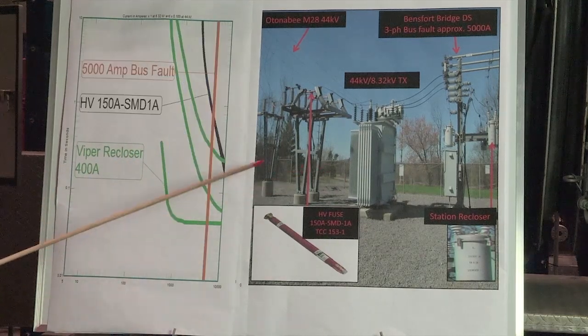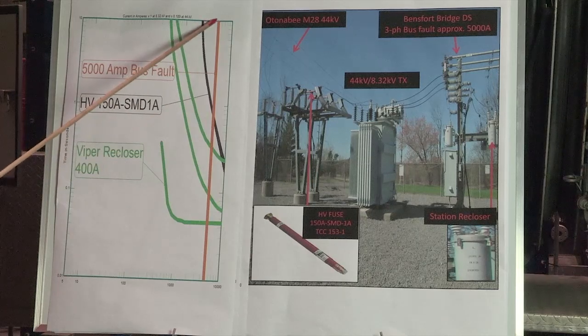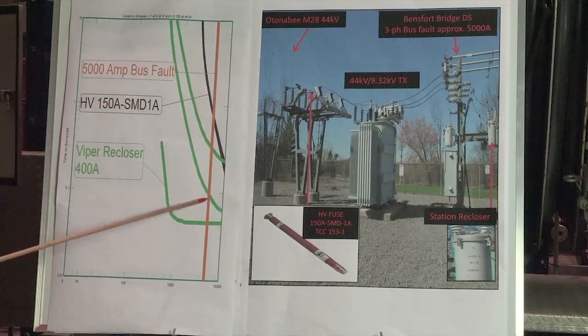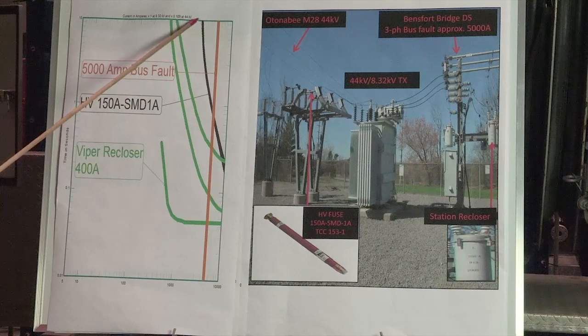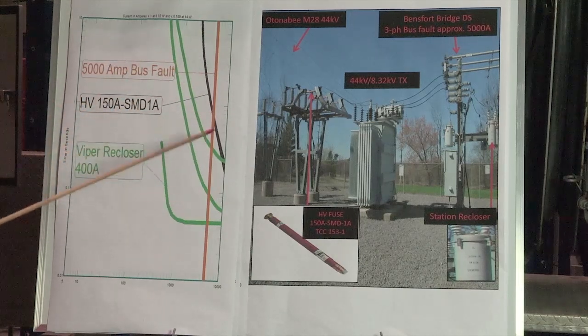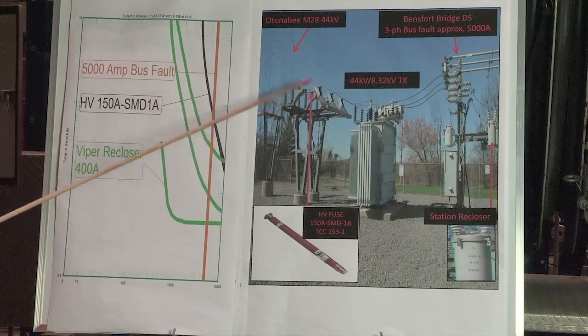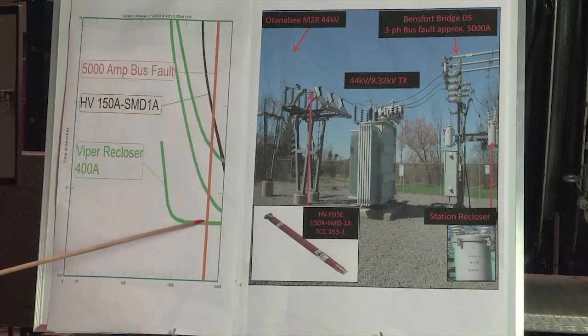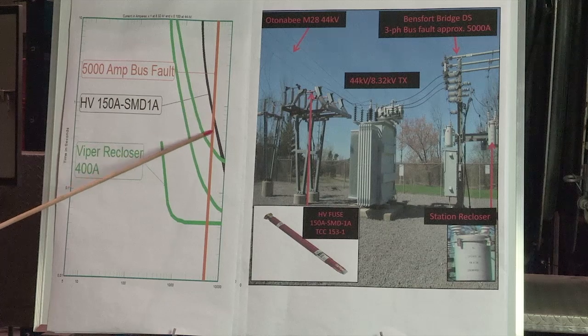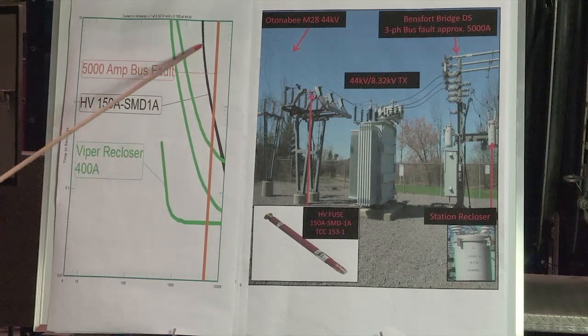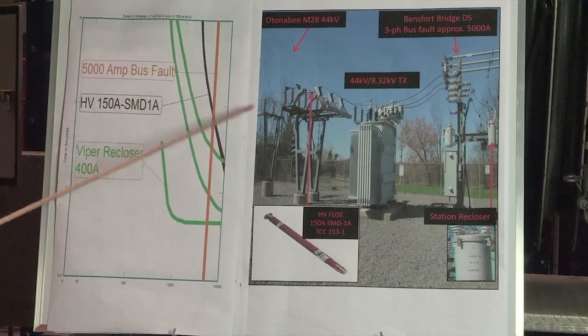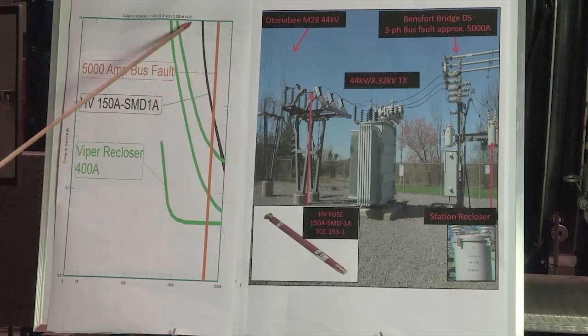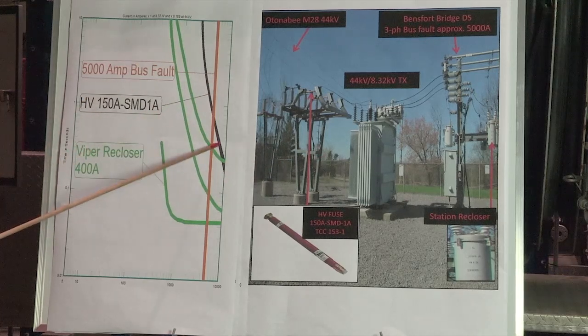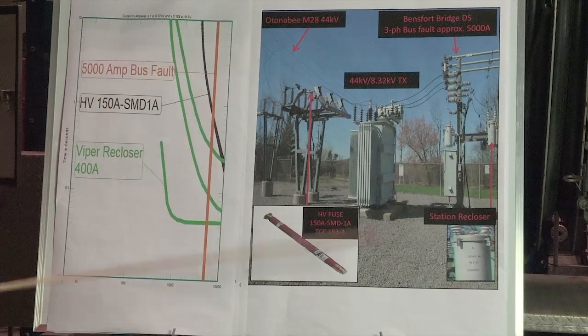So in the next diagram, we're basically going to show this 5,000 amp fault as well at the DS. We got our high side fuse, and now we got our recloser modeled in as well. So if there is a fault on the DS, this recloser is going to pick up this fault before the high side fuse even has a chance to see it, clear the fault hopefully, and if not, then this high side fuse will now clear the fault before the transformer damage occurs.